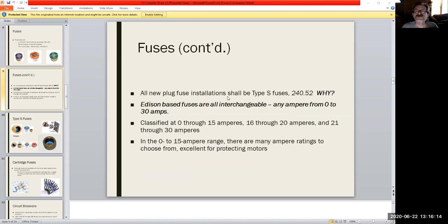So all new plug fuse installations shall be type S fuses, according to Article 240.52. Why? And going through the homework, you should have found that, at least from the ones that I was able to read through. All Edison-based fuses are interchangeable, any ampere from 0 to 30. So how do they rate it? Well, we got three styles from 0 to 15, 16 to 20, and 21 to 30. And these are three sizes that are not mix and match, if you will.